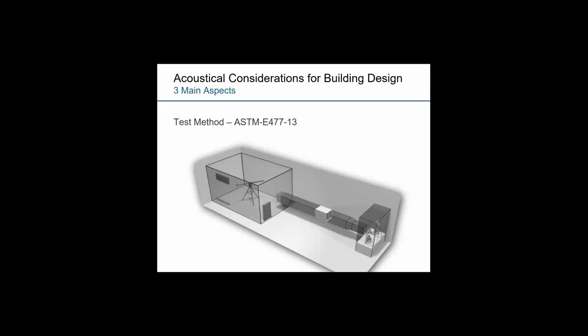So it's a relatively easy standard, but I hope that gives you some clear understanding of how it's set up and why we do that test to determine dynamic insertion loss. And we call it dynamic because it's done under airflow. There's air flowing through here as well as sound, and it's measured at different duct velocities and different duct cross-sectional areas to obtain catalog data for dynamic insertion loss.